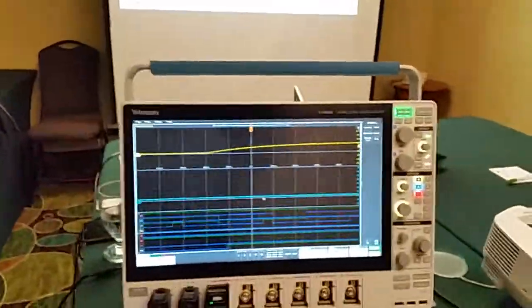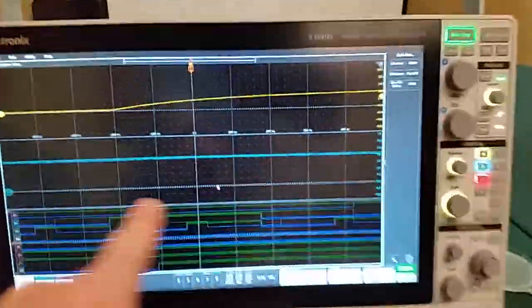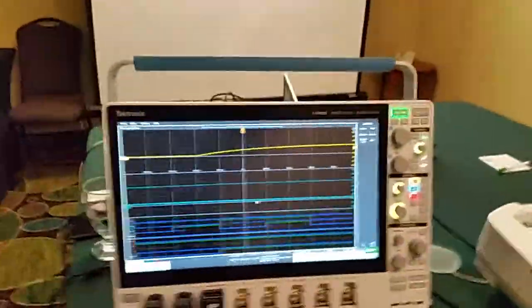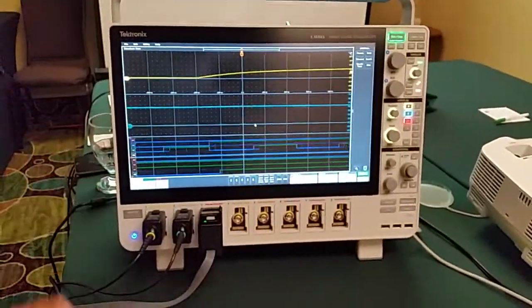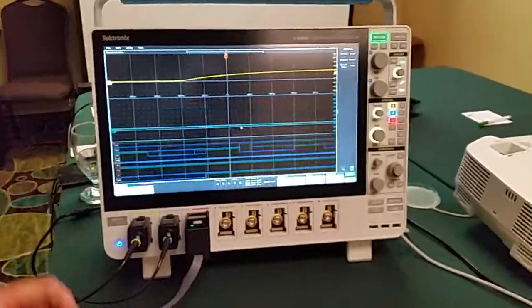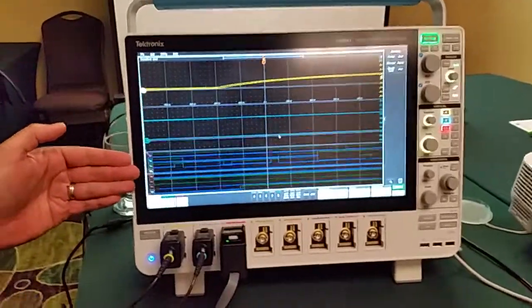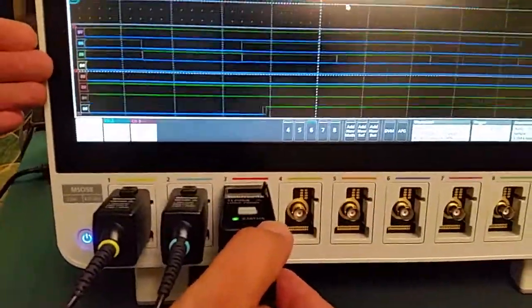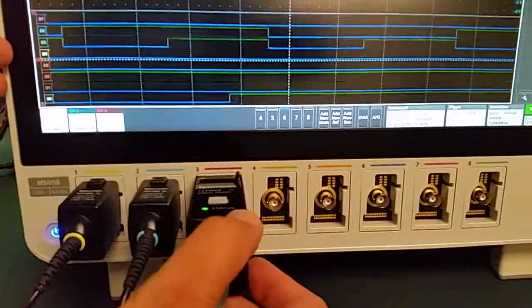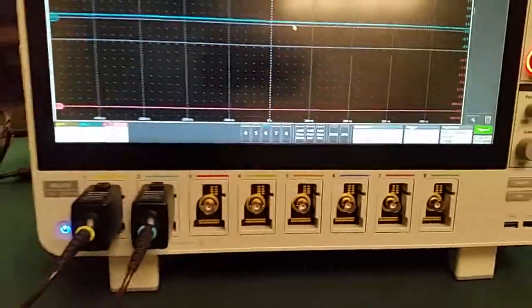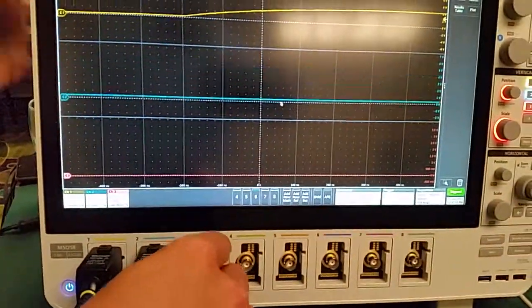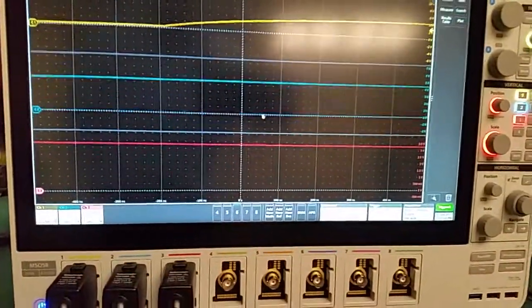The waveforms coordinate to the colors as well on the channel, right? Yes, the waveforms on the screen are matched. And right now, talking about one of the major industry firsts of this instrument, the reconfigurable inputs, right now on channel 3, I have our new Tektronix logic probe that gives me eight digital channels here, and they're displayed here. If I disconnect this probe, channel 3 has converted back to an analog channel. Very good.